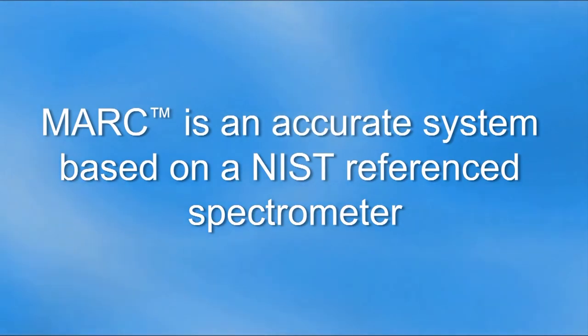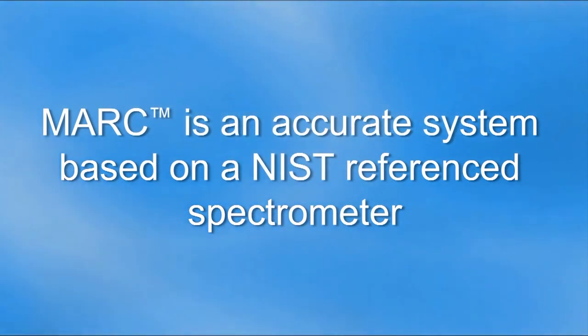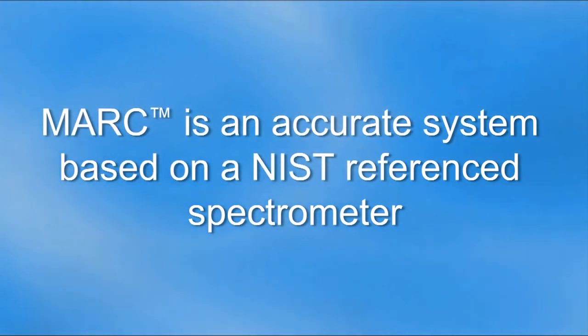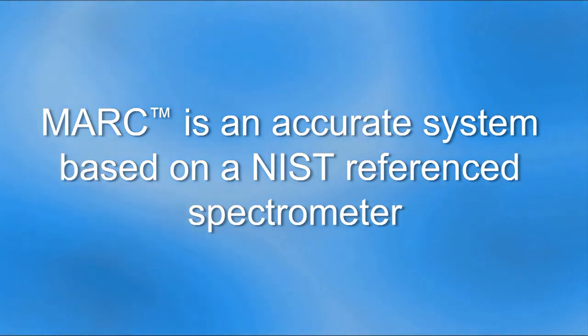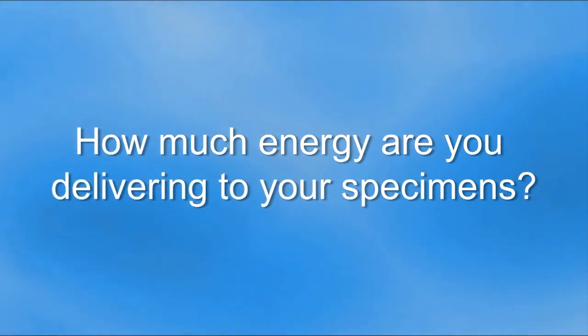This video shows the problems of using dental radiometers for research on resin curing and also for measuring the output from curing lights. The MARC system is an accurate system for measuring the irradiance, total energy, and wavelength, and is based on using a NIST-referenced spectrometer. How much energy are you delivering to your specimens?